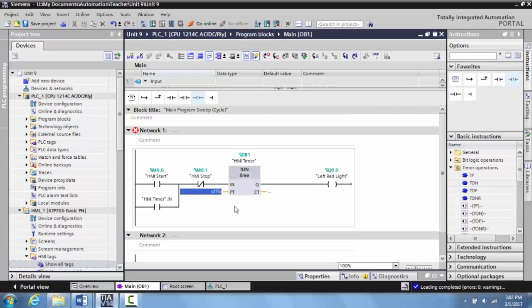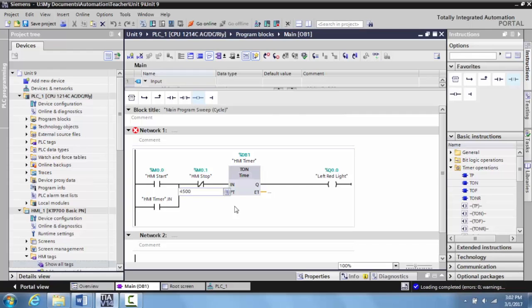Now let's make the preset here four and a half seconds. So remember you're multiplying by one millisecond. So for four and a half seconds, it would be 4500 milliseconds. And you can see four seconds, 500 milliseconds, or that'd be 4.5 seconds.